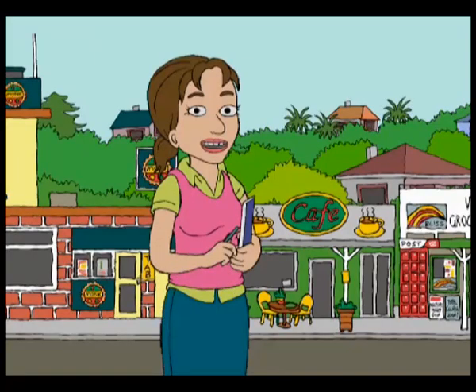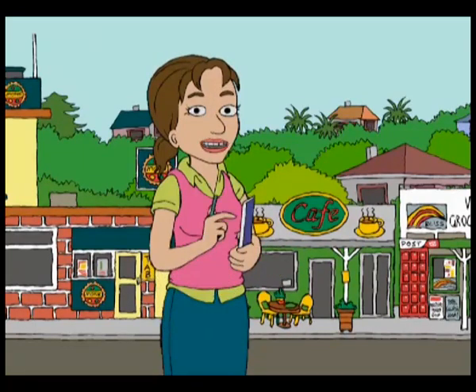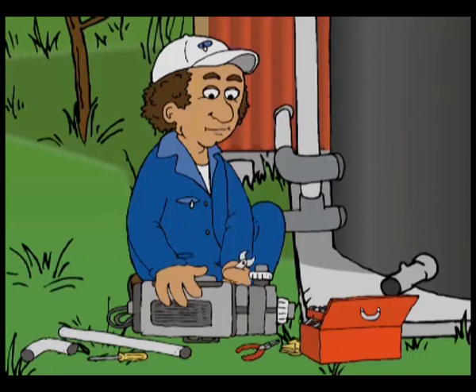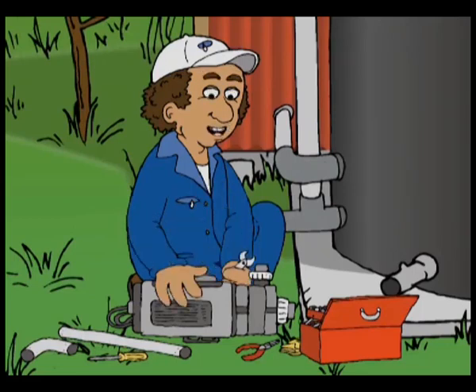Once the treated water has left the treatment plant, we don't want this water recontaminated. In other words, treated water needs to be protected from any contamination that may allow bacteria, protozoa, viruses to get back into the water. But recontamination covers more than just recontamination from pathogens. For example, pump equipment should be selected and installed to prevent recontamination by pollutants that might get in the water, like lubricants from the pumps.